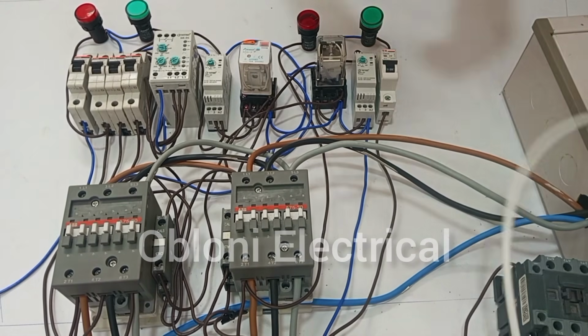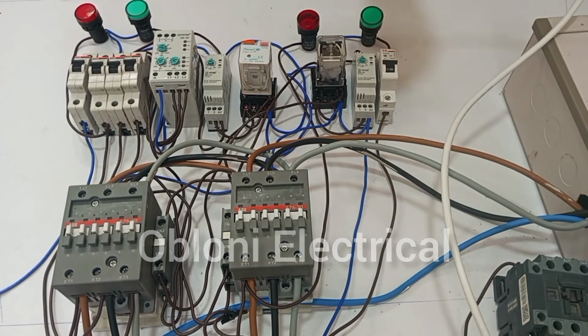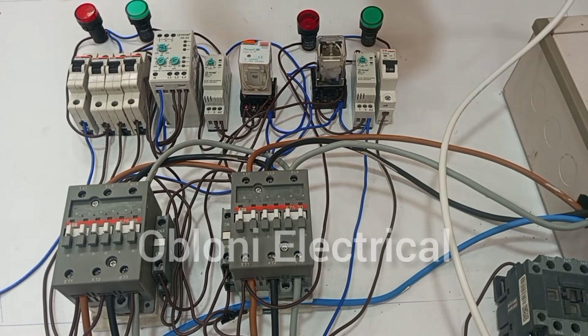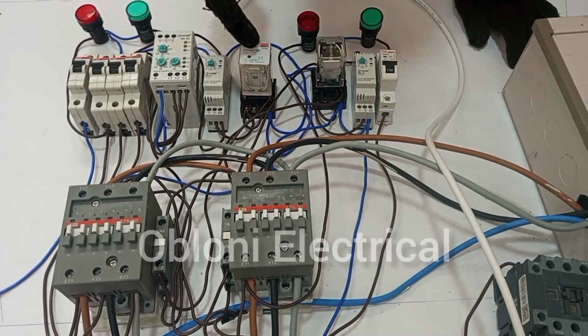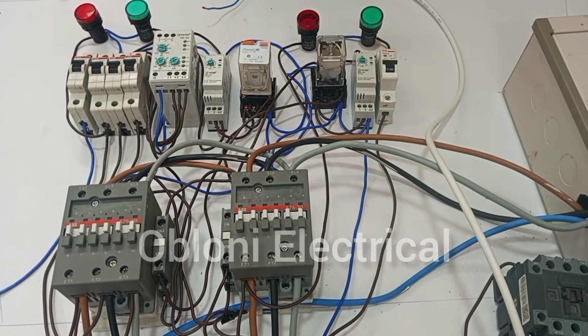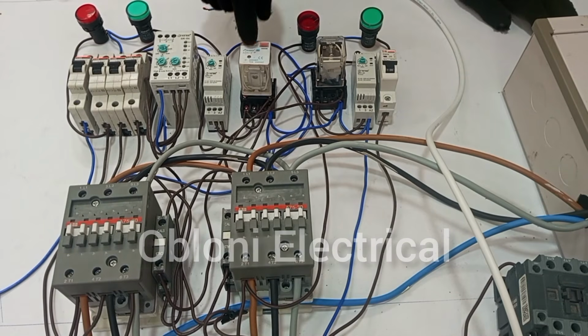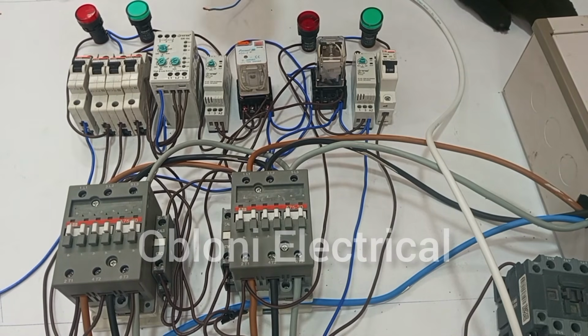All right, so we have these wires coming from two contacts on the generator controller. Then we are wiring these two contacts through the relay that we have used for the main supply. And if you look at the relay, there are three pairs of normally closed contacts, and then there are three pairs of normally opened contacts. One of the normally closed contacts on this relay that I'm using is number 8 and number 11.